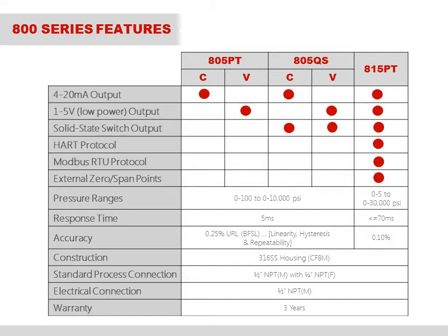Various unique features are offered only by the 815. Those are HART protocol and Modbus RTU serial communications, the external zero-span magnetic targets that are located on the housing. This enables one to set the zero and span points with a magnet. Lower and higher pressure ranges, and a better accuracy of plus minus 0.1% upper range limit or full scale output.